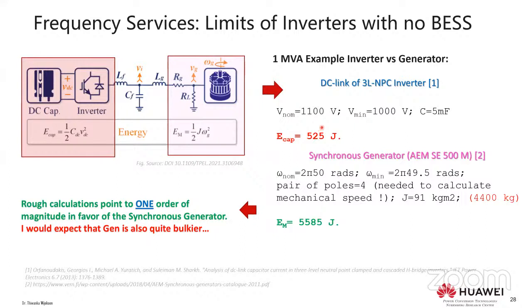A typical 1 megawatt converter may operate at 1100 volts with some electrolytic capacitors, accounting for around 525 joules. If you calculate the similar mechanical energy in a synchronous generator for a similar power range, you're talking about one order of magnitude higher. One can say a generator is bulkier than a converter, but this is the key pain point — if you expect similar behavior from converter-based generation as from a traditional synchronous generator, you're mistaken. You have much lower energy storage capacity to support grid needs.